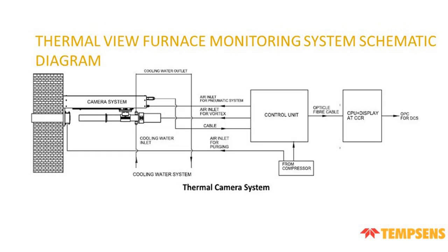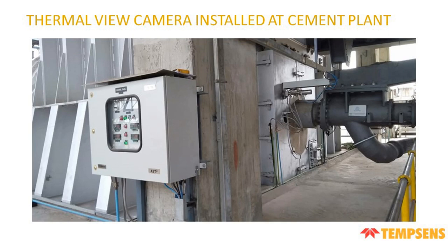Thermal view furnace monitoring system schematic diagram. This is the same as the normal view, the only difference being that the signal comes through fiber optic in the CCR, and we use special software in the CCR to get the thermal camera process data, and we also have OPC connectivity for the plant DCS. Thermal view camera installed at a cement plant.